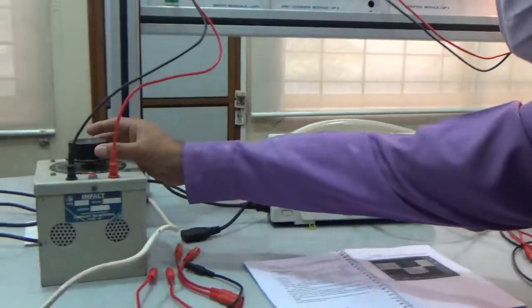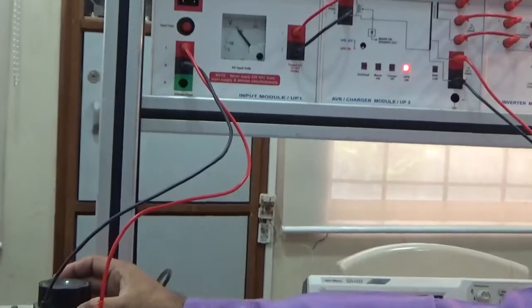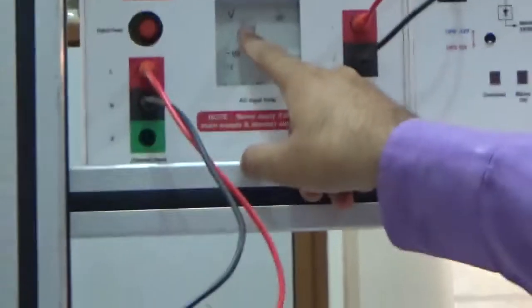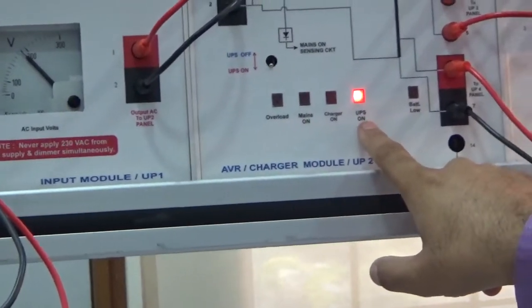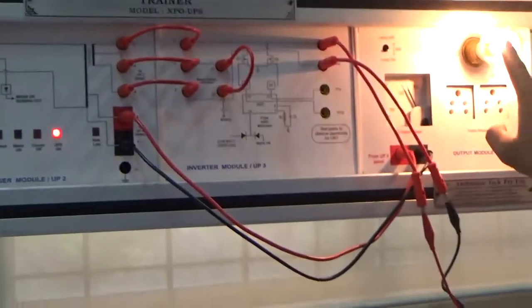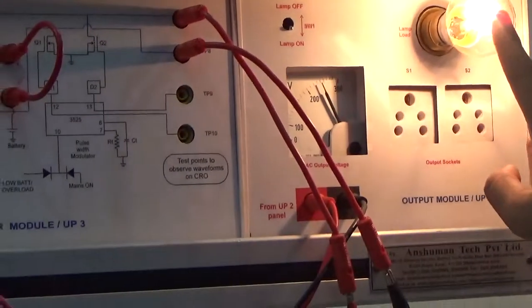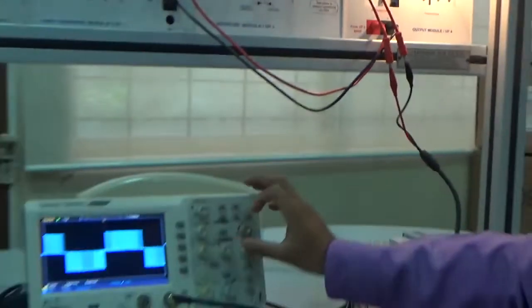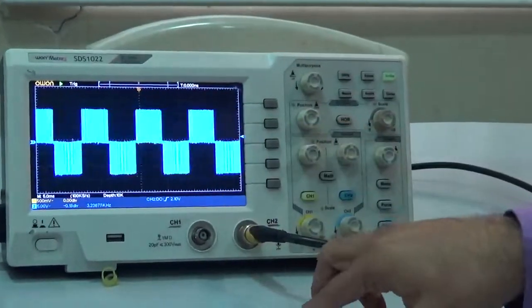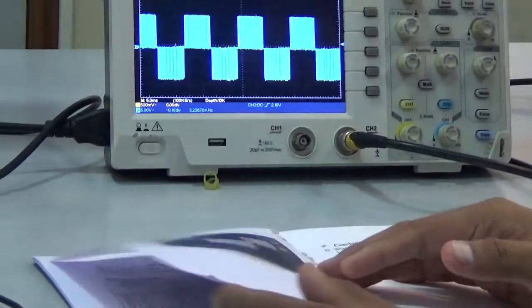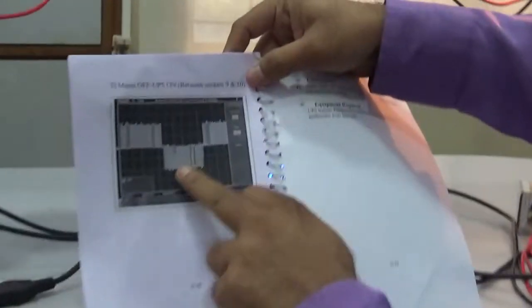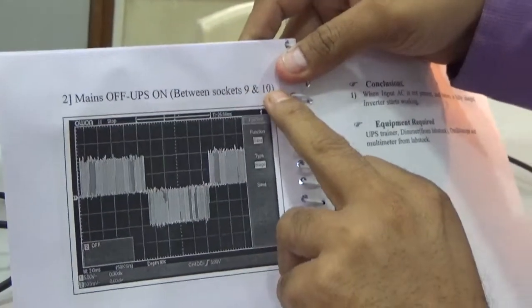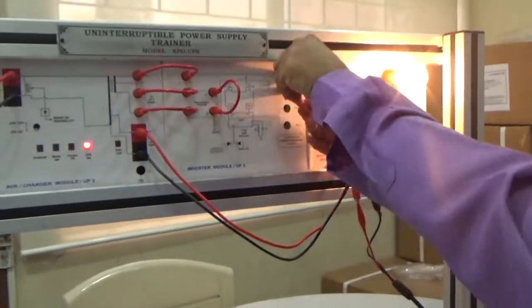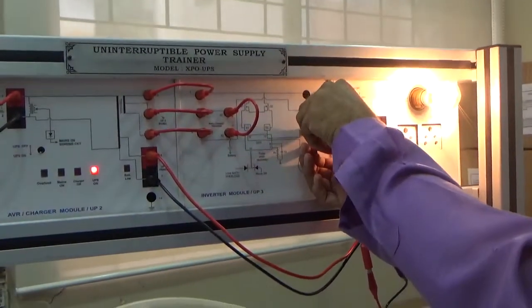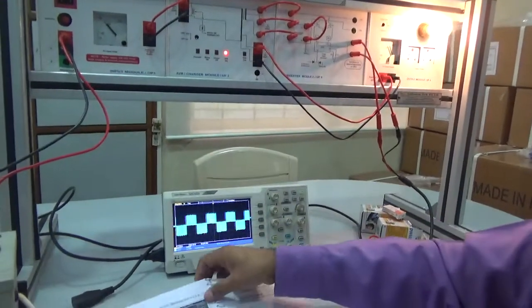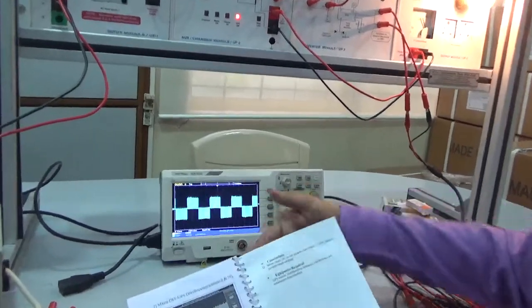Now we will reduce this below under voltage. Now this voltage is below 190. Now mains is off and UPS is on. In this condition, here we are getting 240 volt at the UPS output, and here we are getting the waveforms. Now again, another waveforms are between tag number 9 and 10. Mains off, UPS on.